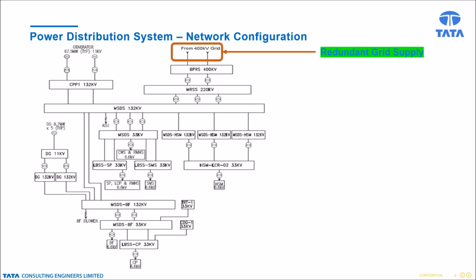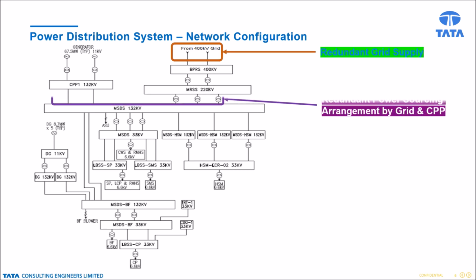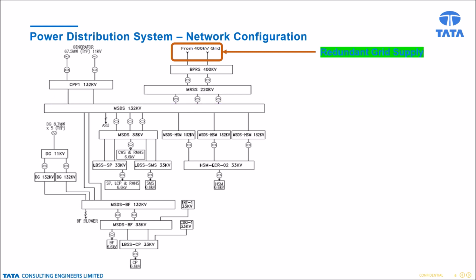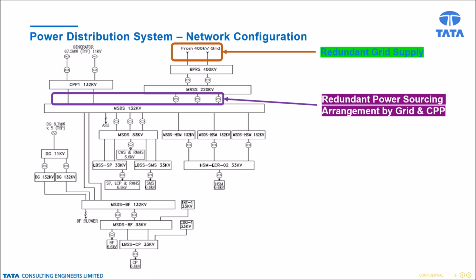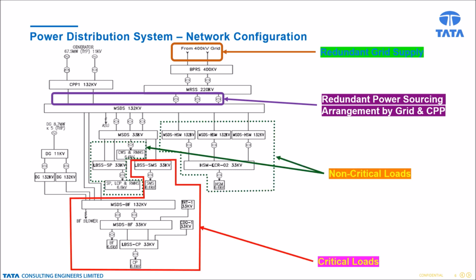While sourcing grid power, quality of power is also to be explored with respect to frequency and duration of grid interruptions, current and voltage harmonics among other things. Power network should be configured considering 20 to 100% redundancy such that outage of one transformer or feeder does not cause power interruption and jeopardize the operation of the process plant connected to the distribution network. Quantum of critical and non-critical loads has to be assessed after discussion with process and operation group. Under any contingency condition, continuity of power supply has to be maintained for critical loads.